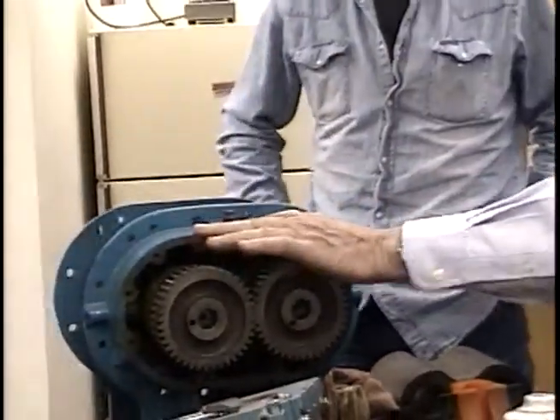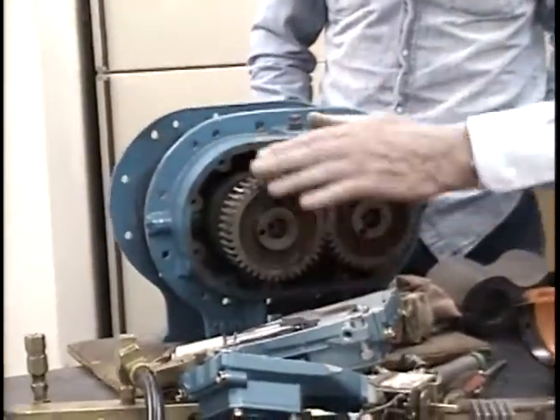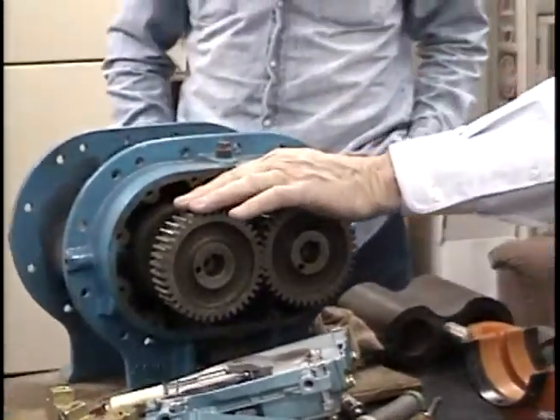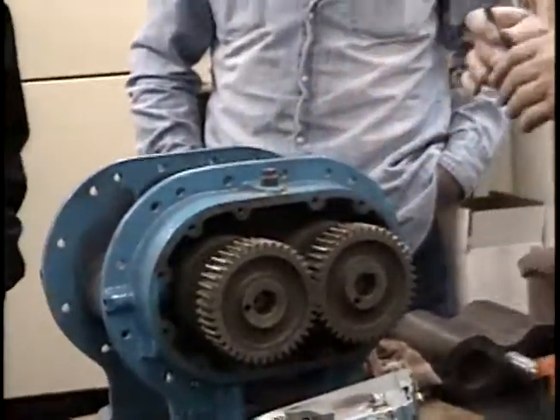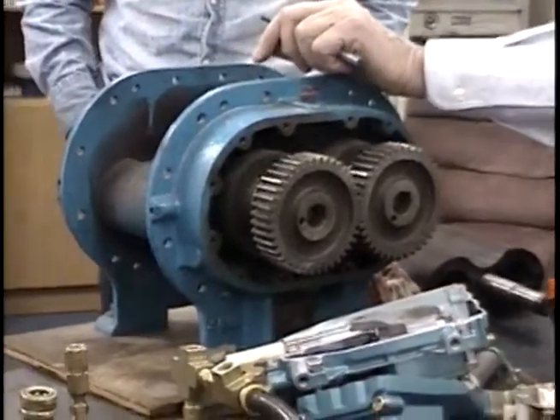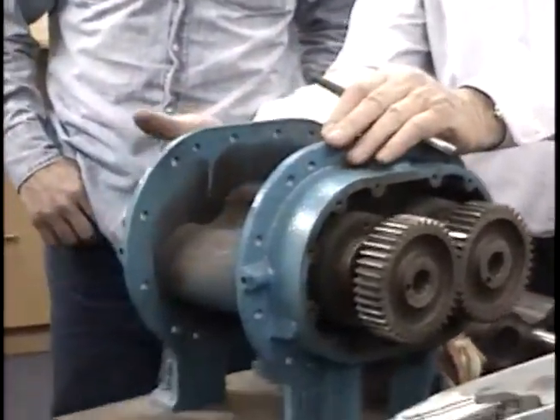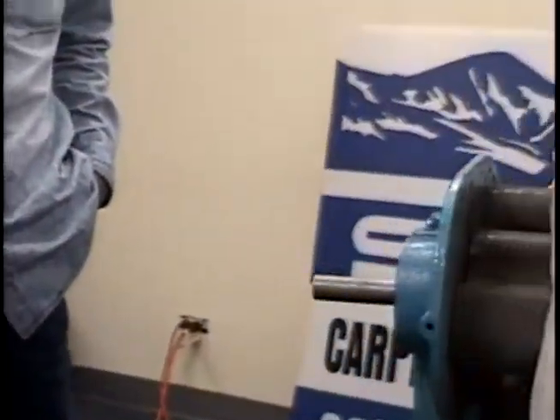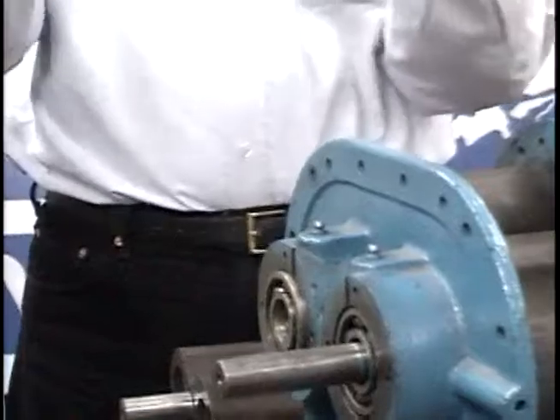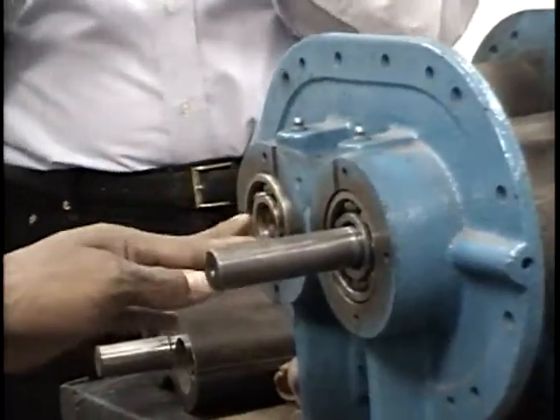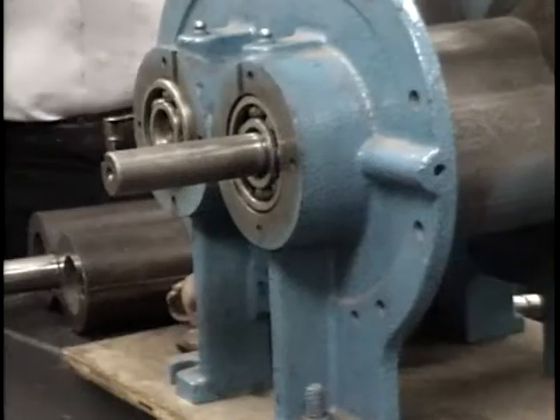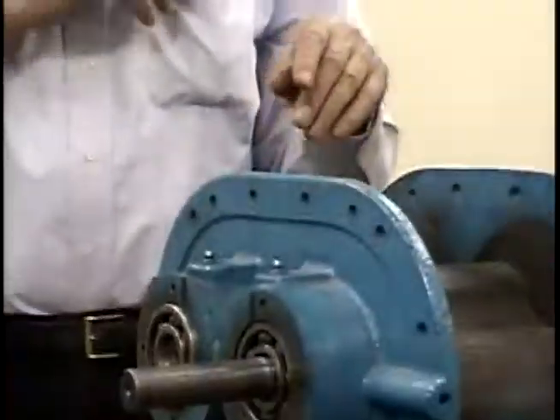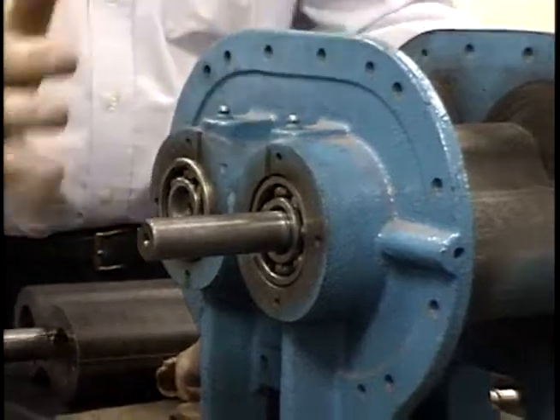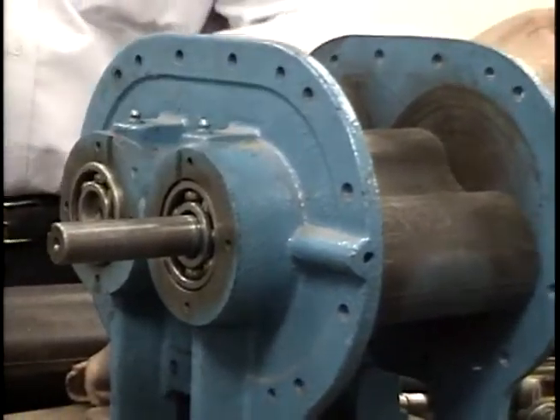That takes care of this end of the blower, keeping a certain amount of Tuthill blower oil in it, like the differential or transmission in your automobile, a certain level of oil. On this side, there are two grease zerks, and we need to grease these bearings periodically. Remember we've been looking at maintenance, but we haven't looked at the chart yet. Our maintenance checklist will tell you how often to lubricate those. So that takes care of both ends of the blower: the grease zerks and the oil in the crank.